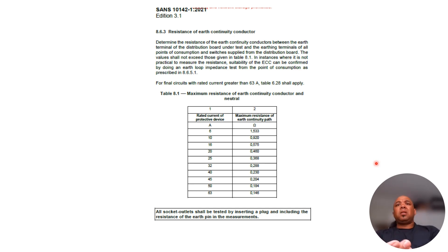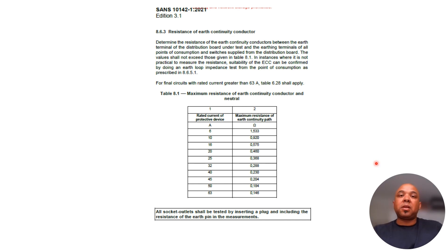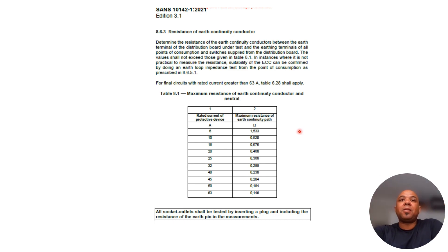Besides continuity of bonding, you also need to do a polarity test on each socket outlet, check the voltage at each socket outlet, and more — all prescribed in SANS 10142. So if somebody says they'll do it for 200 or 300 rand, it's probably not worth the paper it's written on — unless they've already lined you up for a big repair quote.